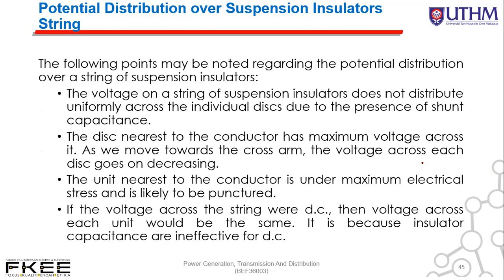And then some points that may be noted regarding the potential distribution over a string. Pertama sekali, the voltage on a string of suspension insulator does not distribute uniformly across the individual discs due to the presence of shunt capacitance. Okay, ada shunt capacitance, so dia punya voltage tak distribute uniformly. Kemudian the disc nearest to the conductor has maximum voltage across it. Paling dekat dengan konduktor paling tinggi dia punya voltage.